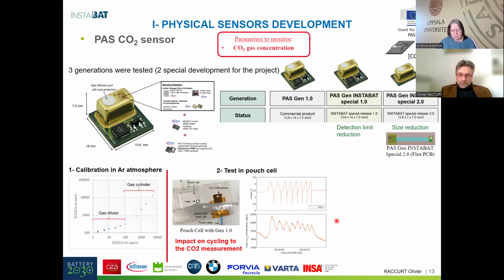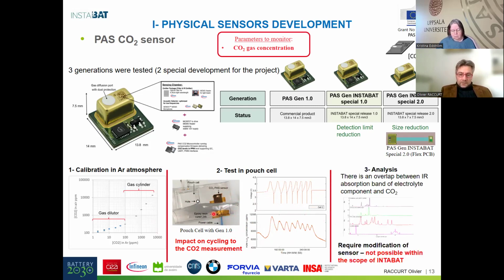And there is a lot of question after this experiment, and we explore in more detail what happened with the sensor. We identify that the sensor was based on the absorption peak of the gas in the infrared area of the CO2, but this absorption is at the same wavelength as the infrared peaks from the electrolyte components, such as the carbonate. And that's why we don't measure the CO2 in this case, but we probably measure other things. There is a lot of interference between CO2 and the other gases inside the cell, and it's not possible for this sensor to measure the CO2 only. We identified during the project some solution for that, but it was not possible to implement it during the project.